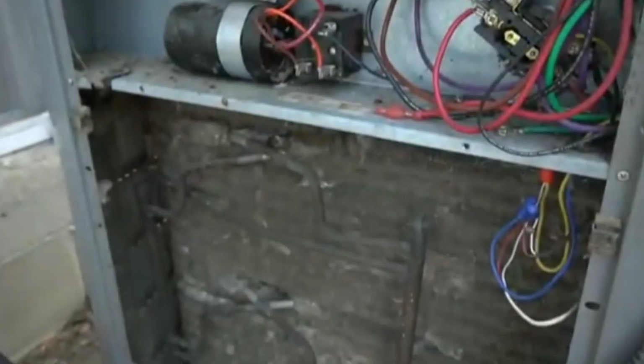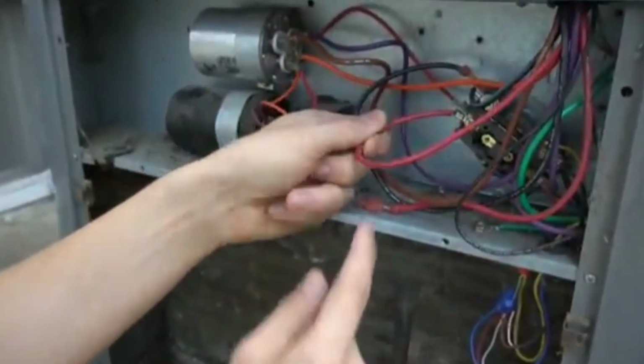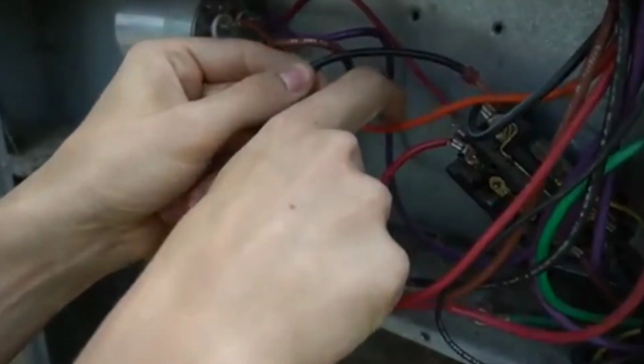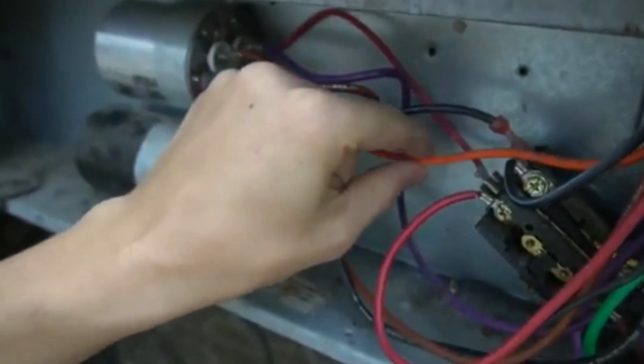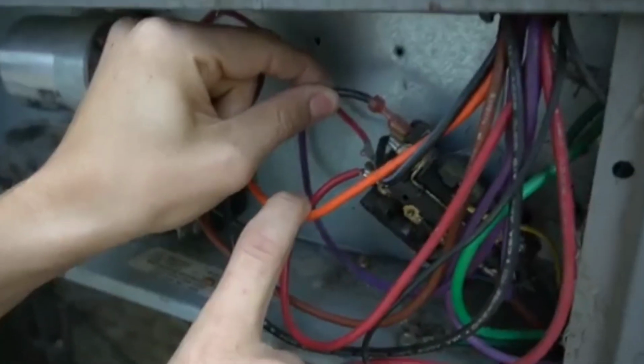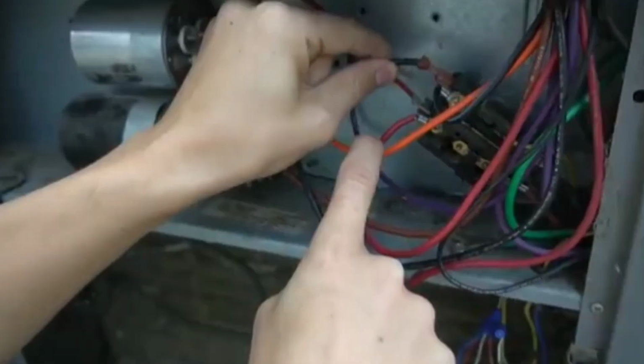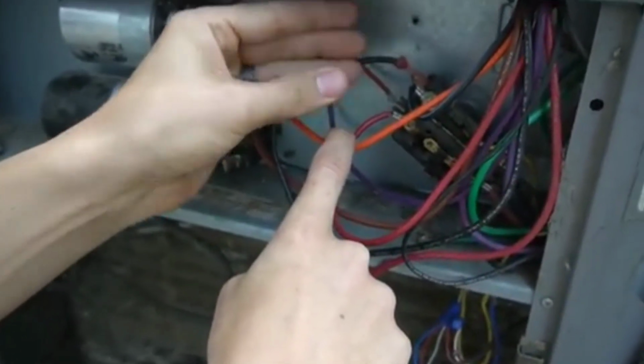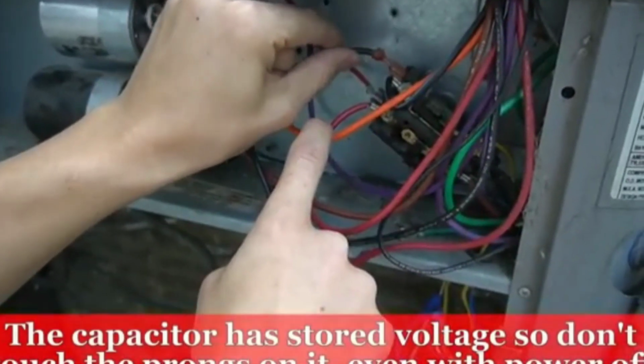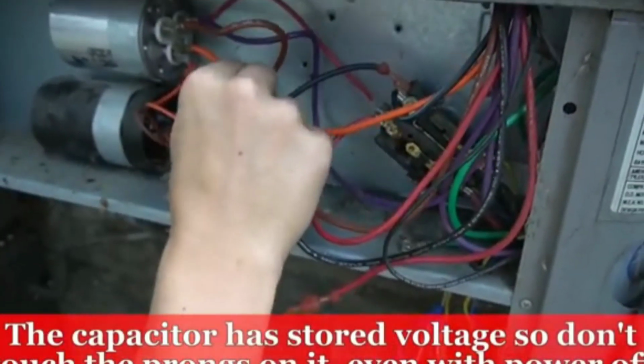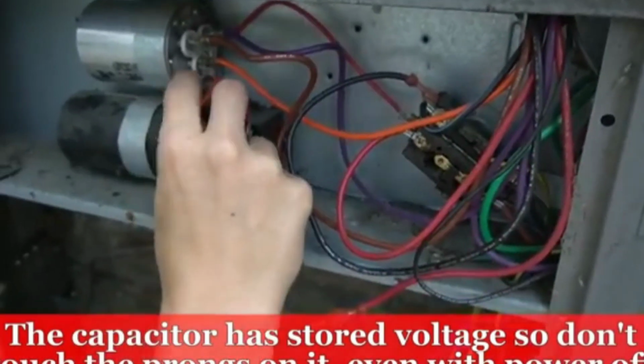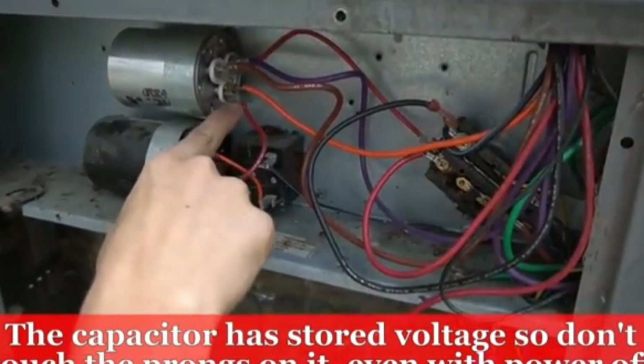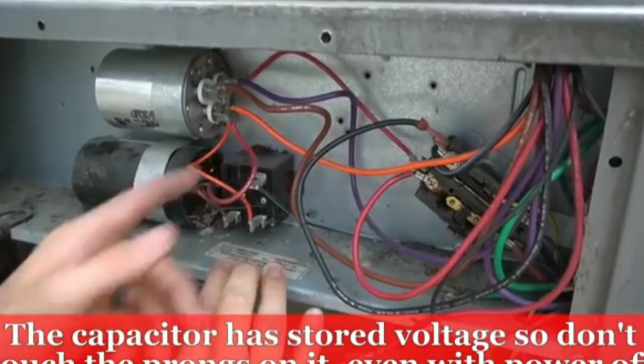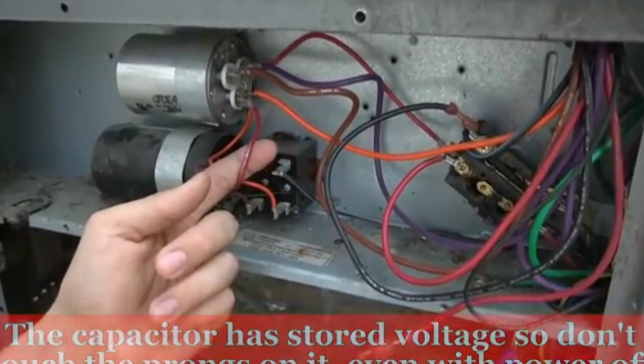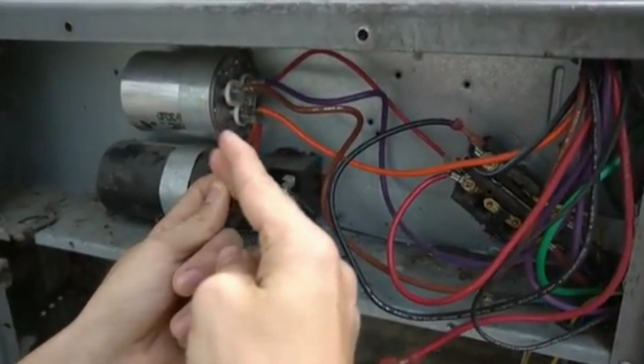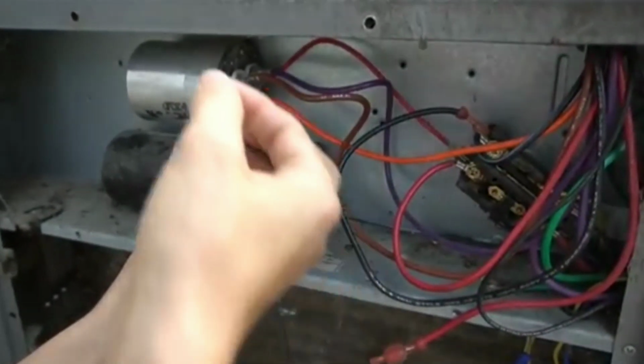But basically, after you open this up, just look at all the connectors where all the wires go. Make sure nothing is brittle and falling apart. Once in a while I'll come to a unit, I'll grab a wire and just wiggle it a little bit, and it just falls apart completely. Like the connector just kind of crumbles as I yank on it a little bit, not a lot of pressure. So just kind of tug on all the wires, take a look at them, examine them. If you do notice some broken connectors, or maybe they're burnt or corroded, what you can do, if you're comfortable with doing that, is just snip that piece off, strip the end of the wire, and put a new connector on there.